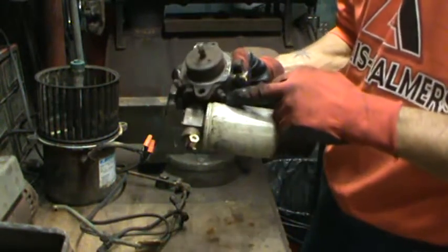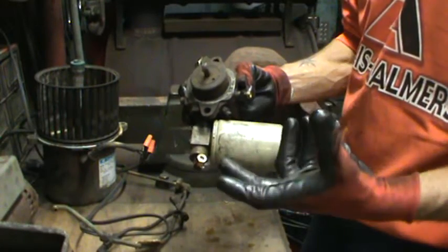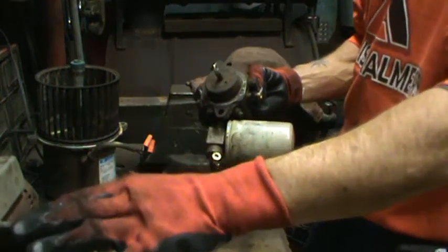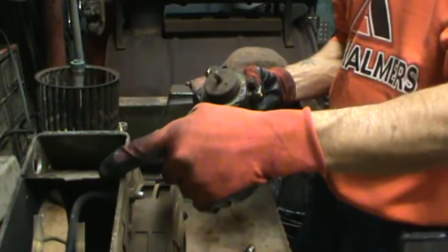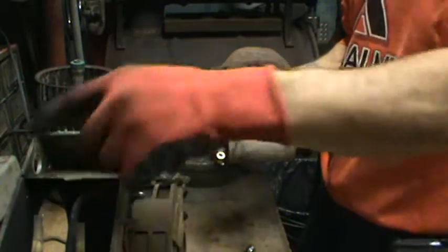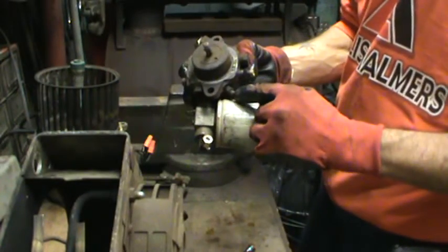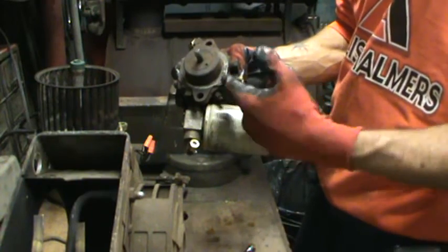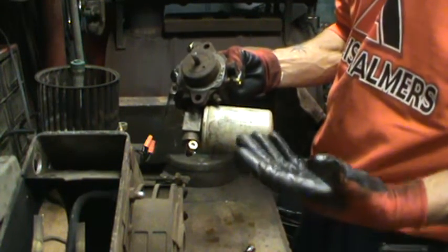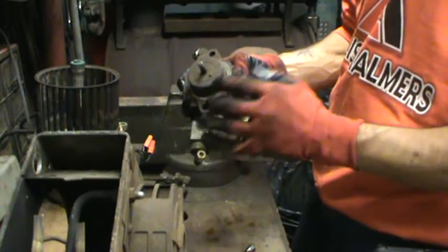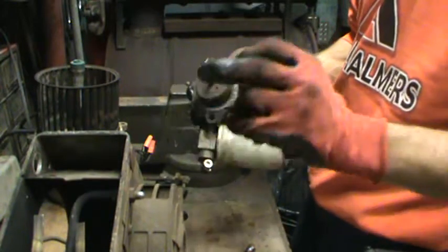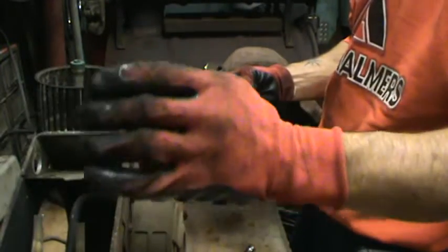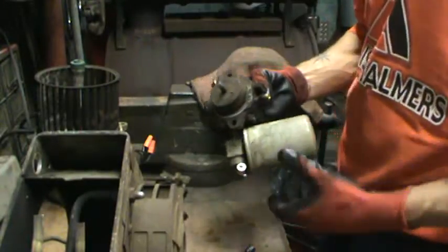In the event that you do need to prime them, you flip your igniter over so it won't make contact and won't try to light it. Then you open this bleeder valve here and run it until you get a steady stream of fluid out, then lock that down. That purges the pump head. Then you can put your igniter back over the top, fire it up, and you're off and running to the races.